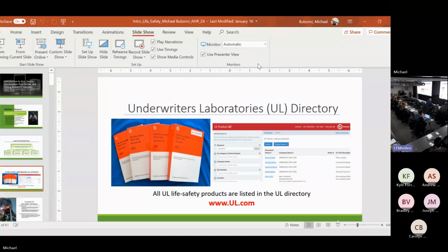We see them on ceiling radiation dampers all the time. So if you're doing multifamily, low-rise wood truss, high-rise steel truss, you might see a Warnock Hersey, an ETL, or an Intertek rated ceiling radiation damper. But for the most part, fire and smoke dampers, we talk about UL.